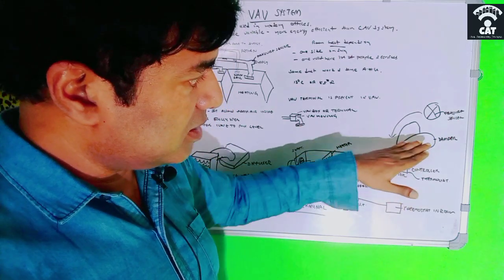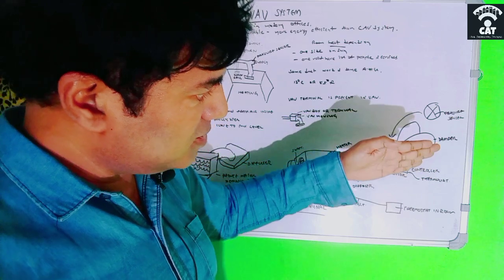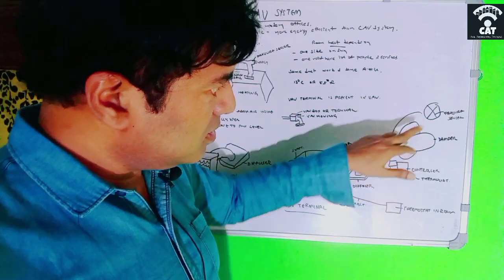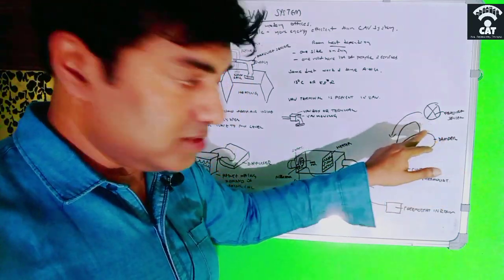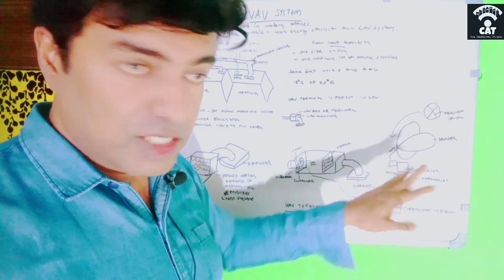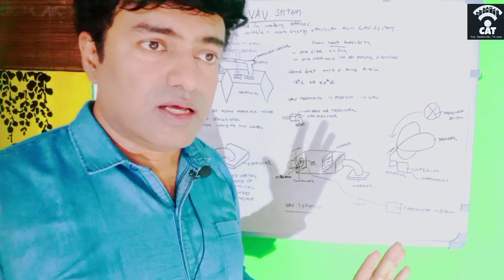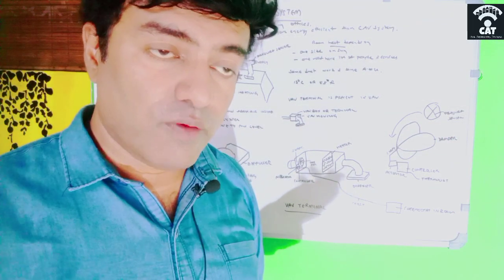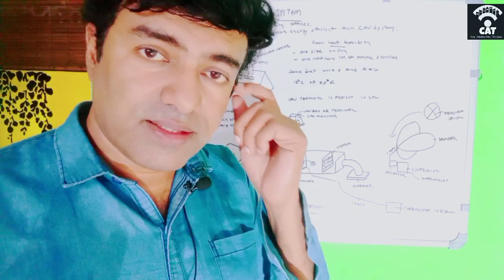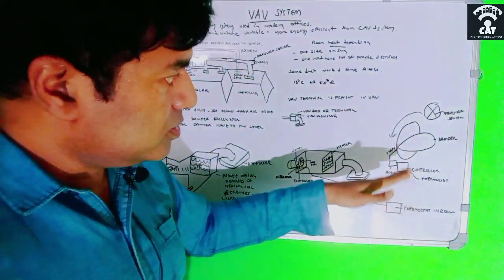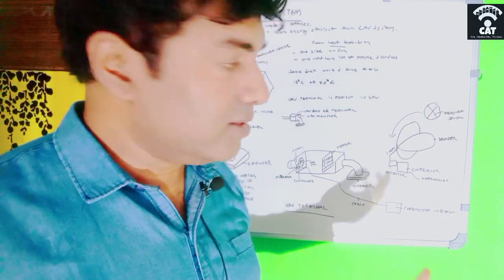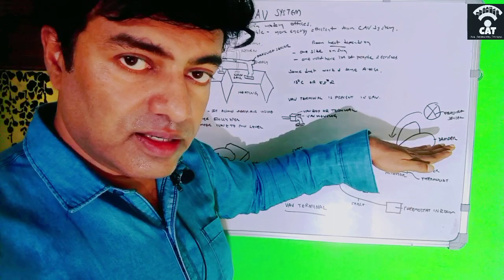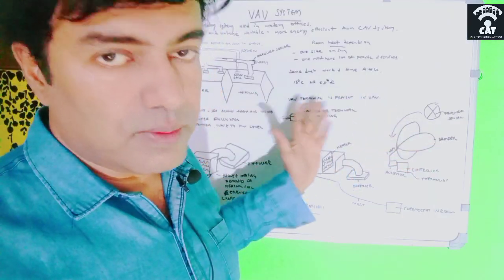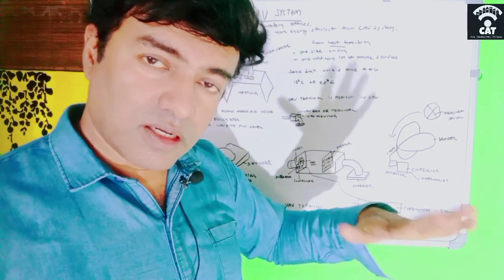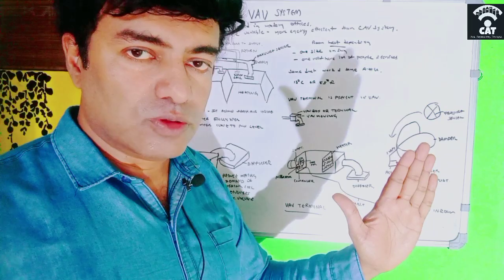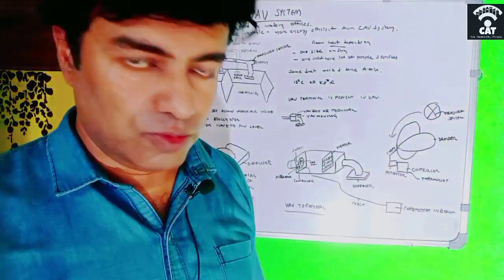See, this is the direction in which the damper is fully open, like this. If it is like this, it is slightly closed. It will go like this because this circular hole will be fully closed by this circular metallic sheet. But it will never close fully, because whatever the temperature difference, there should be a constant fresh air supply into the room. So in order to maintain that, the damper will never be closed fully. When the room demands more cold air, the damper will be in the horizontal direction, so that maximum air will come inside the room. If it demands less cold air, then it will go like this, so that it will allow less cold air to go inside the room.